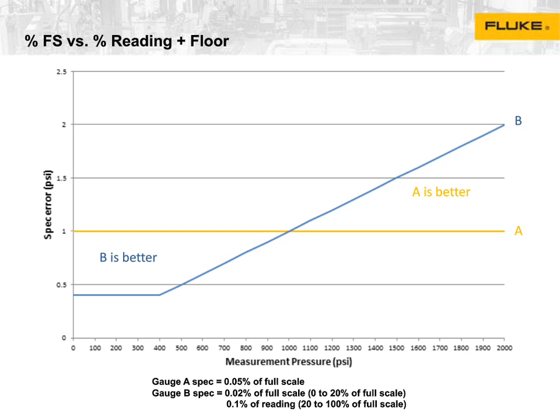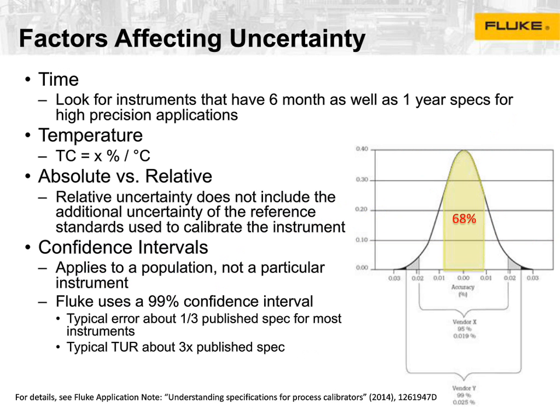So last, before we move on to the next topic, I'd like to talk a little bit about four main factors that affect uncertainty. And we're going to get into this a little bit more in the next section when we talk about gauge verification. But I want to introduce the concept here. And so there are four main factors that will affect the uncertainty of your gauge. Time, temperature, whether it's an absolute versus a relative uncertainty, and what the manufacturer's confidence interval is.